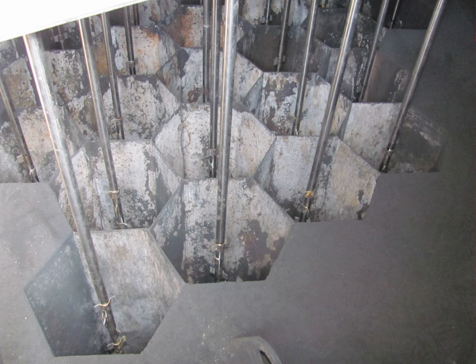Disruptions of the normal corona process greatly reduce the ESP's collection efficiency, which in severe cases may fall below 50%. When back corona is present, the dust particles build up on the electrodes, forming a layer of insulation. Often this cannot be repaired without bringing the unit offline.